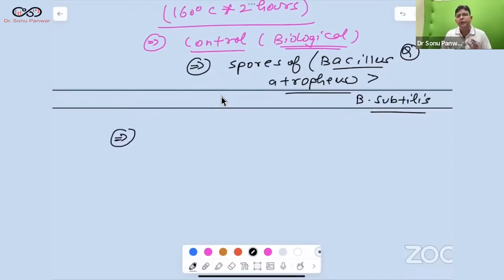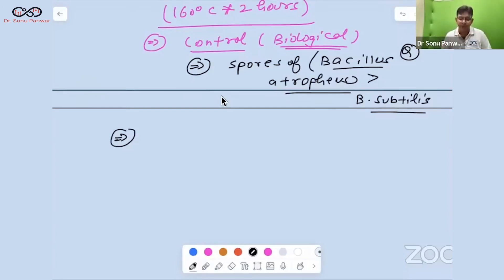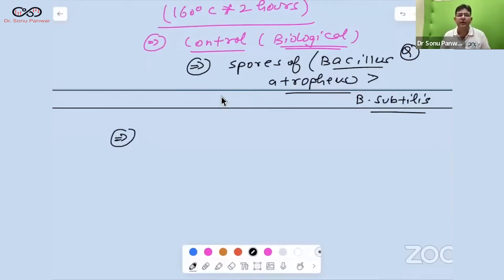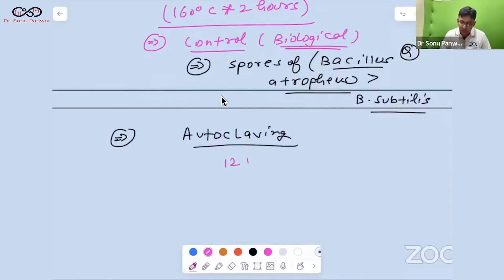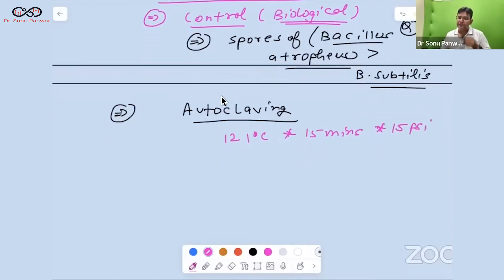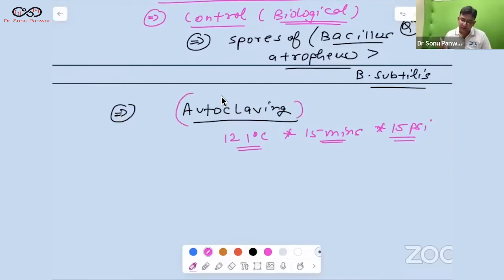For moist heat sterilization: below 100°C you have pasteurization and inspissation; at 100°C you have tyndallization; above 100°C it is autoclaving. The standard temperature and pressure for autoclaving is 121 degrees centigrade for 15 minutes at a pressure of 15 PSI (pounds per square inch).